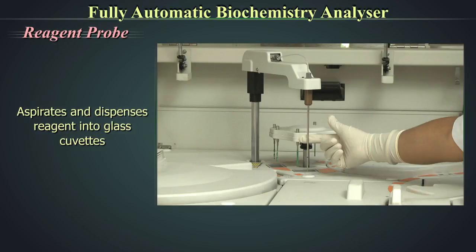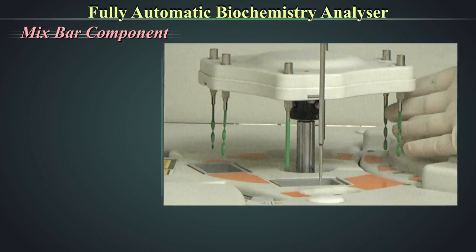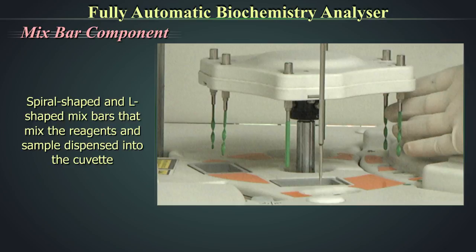The refrigerated compartment houses reagents to ensure their integrity. The reagent probe aspirates and dispenses reagent into glass cuvettes located in the cuvette wheel. The mix bar component houses spiral-shaped and L-shaped mix bars that mix the reagents and sample dispensed into the cuvette.